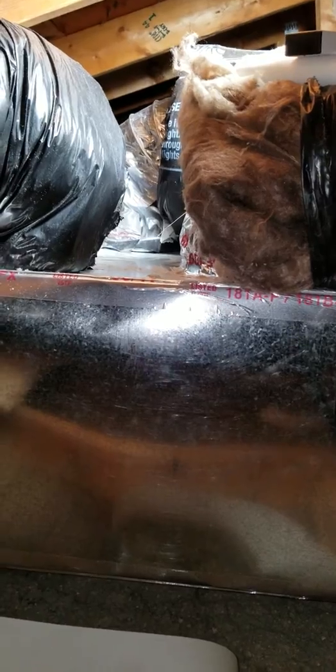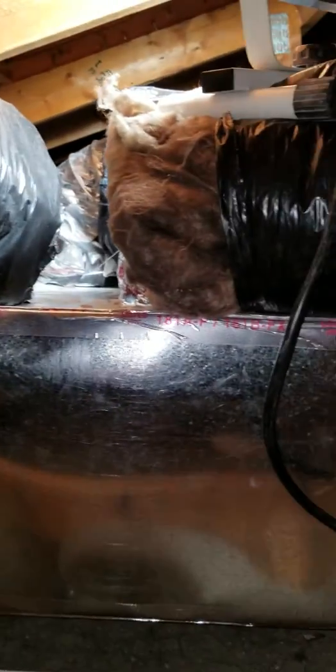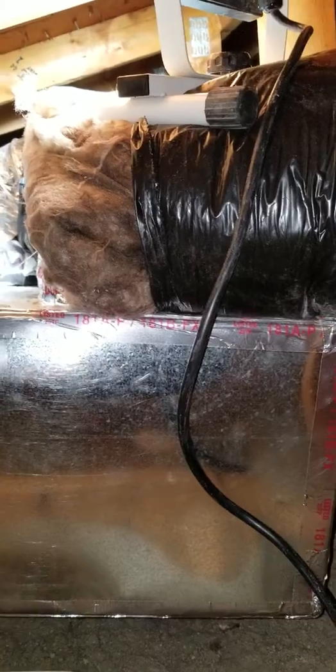On top of that, they don't have a whole lot of insulation up here. So we're going to go ahead and re-insulate everything — we're going to spray foam this trunk to help seal it up and keep it better insulated, so we're not losing so much heat out of this trunk into the attic. With very small attics like this there's not a lot of room for extra ventilation, so it's important to keep this as airtight as possible as far as this trunk is concerned, and stop that heat loss from dumping itself into the attic.